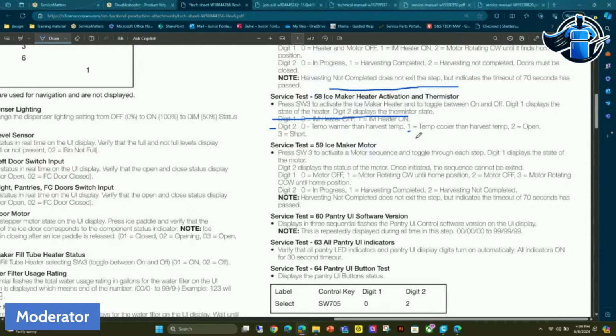Sometimes that will be followed by an E5 fault code, but let's say the day before you showed up, the customer had a power outage. That fault code would have disappeared on you. That's why it's important to always follow up by doing test 58.